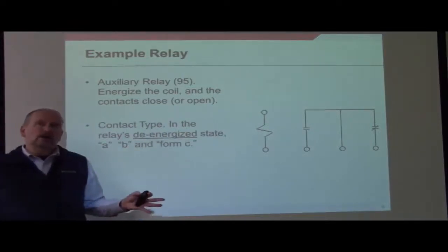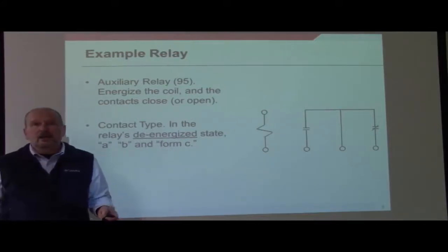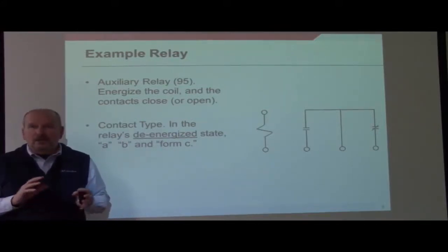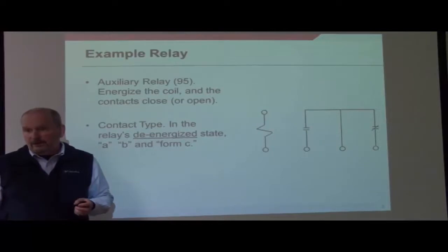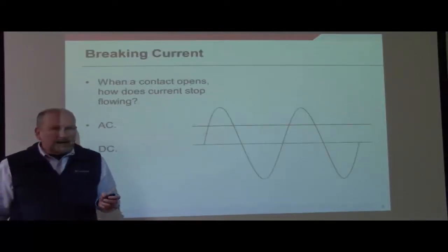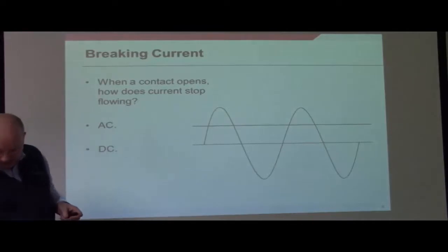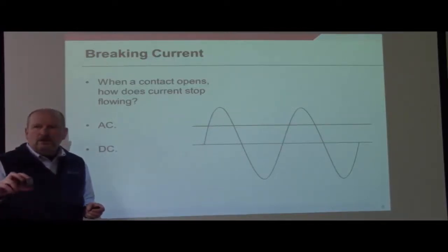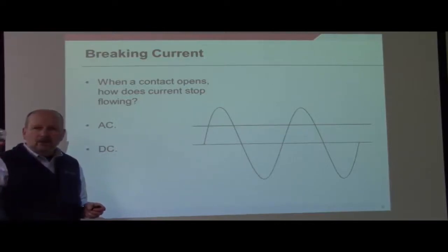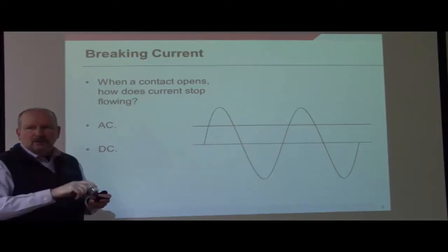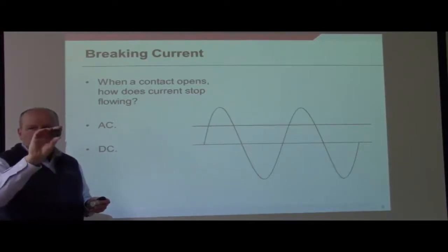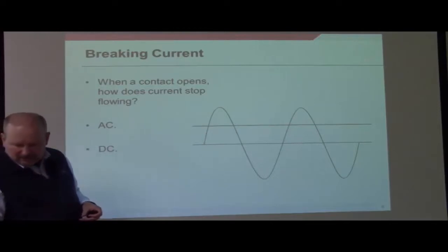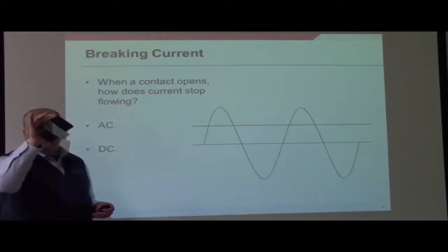Now, a key part of control engineering is that you always show the devices on your drawings in the de-energized state. Really fundamental and important, otherwise it will cause great confusion. Okay, an interesting facet of these, and I've got three examples that I'll show you here in a moment, is that each of them has a current rating for the contacts involved. And I'm holding up one that's a little flash cube relay. And then here is a smaller version of that. And I'll show a close-up of these here in a moment. And then the same exact type, but a much larger version of it.